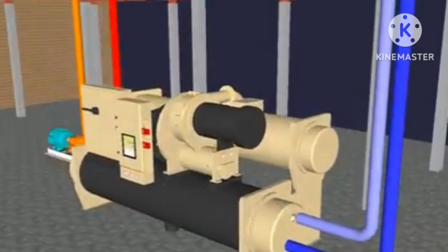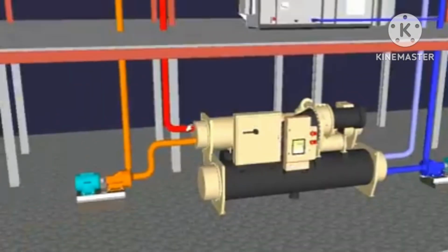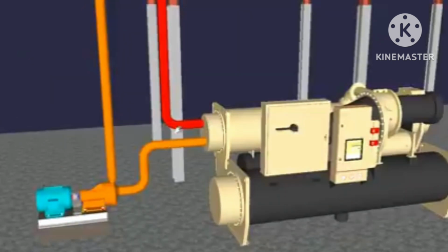So now that the heat in this pipe here has been transferred over to the condenser side, the condenser then sends this water, which is now called the condenser water, up to the tower. And in this instance, I've coloured this pipe red so that you know it's a higher temperature, and in this example it's about 35 degrees Celsius, and it's at a flow rate of about 58 litres a second, being sent up to the cooling towers. That can change as it's just on this design for illustration purposes.